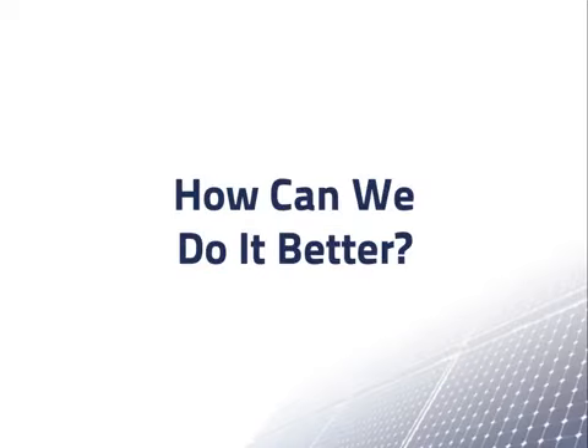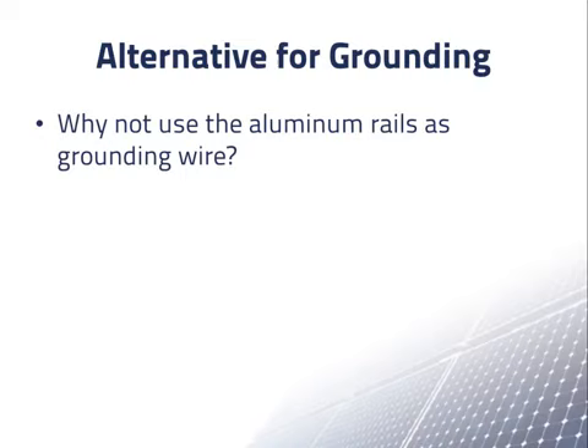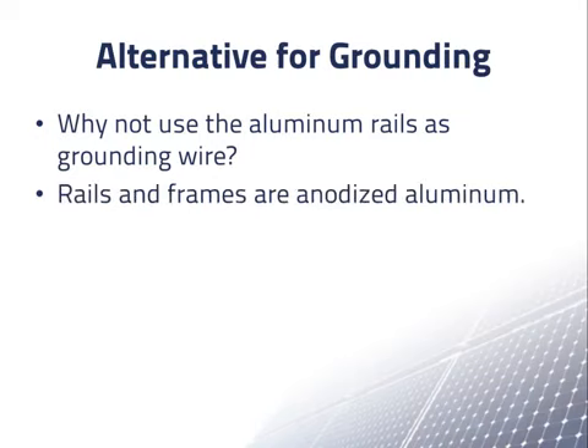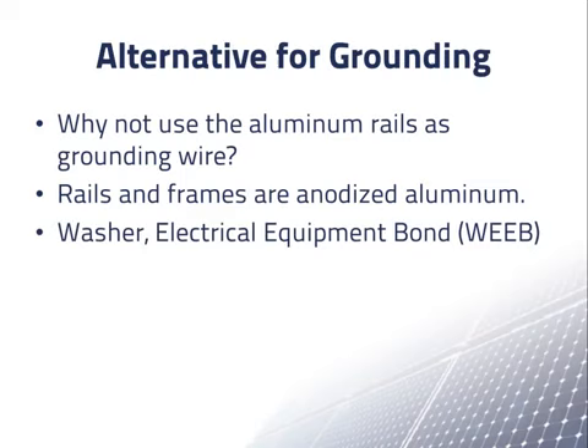With all of these problems and potential for errors, people started to wonder how we can do it better. People started to think, why not use the aluminum mounting rails as grounding wire? After all, they're metal, they're thick, and they already are in contact with the aluminum frames. However, both the rails and frames are anodized aluminum. This means that they both have non-conductive surfaces covering the conductive metallic interior. This led to the development of the washer electrical equipment bond, or WEEB connector.